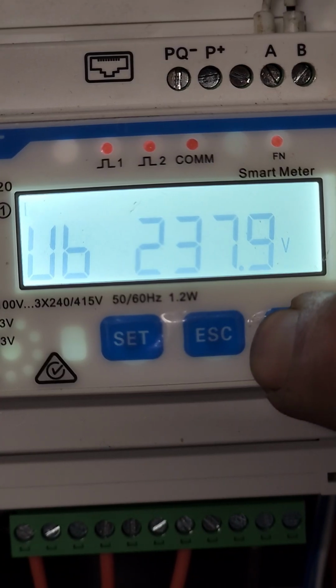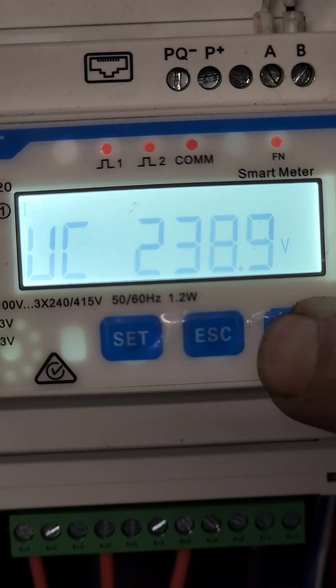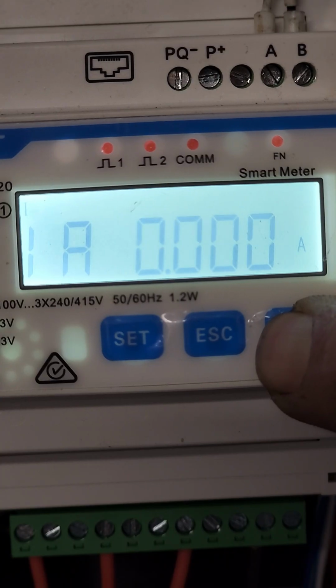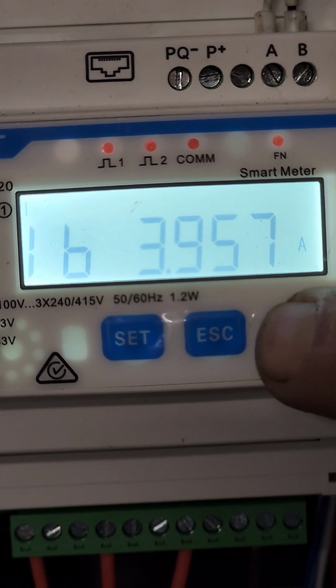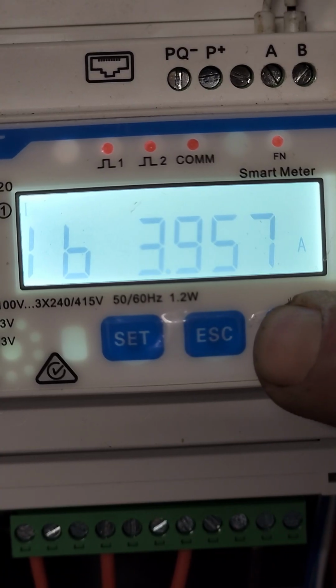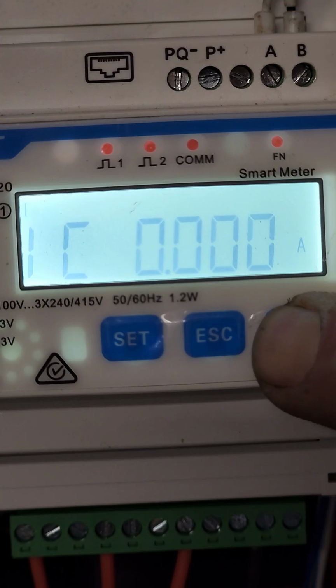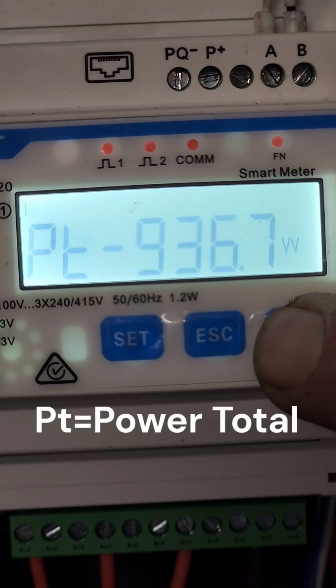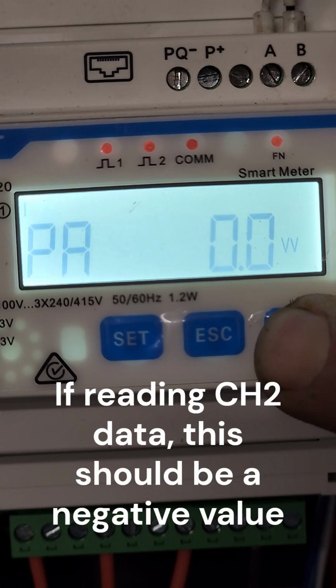So UA, UB, UC, that's only the voltages. We've already checked that they're the same. IA, IB, IC. So as you can see, B there I was pulling 3.9 amps. However, I've got no generation, but why am I exporting? So A phase, obviously it's 0.